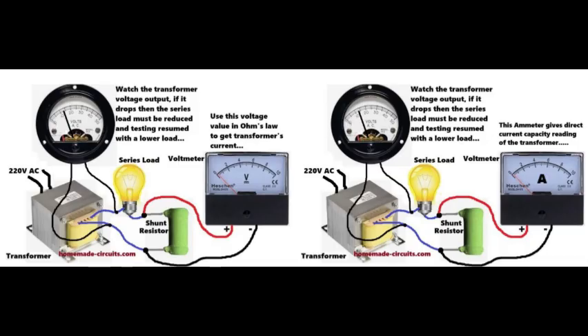Example calculation. Let us say we put a 0.05 ohm shunt resistor. Now, during the test, we measure voltage drop across shunt equals 0.75 volts. So current equals 0.75 divided by 0.05, which is equal to 15 amps. If transformer output is still near 12 volts and heating is moderate, then we say this transformer can give 15 amps safely. But if at that point the transformer body is getting hot or buzzing or voltage dropped below 11 V, then we stop and say transformer max current equals maybe 12 amps. So we decide that 12 amps is safe, 15 amps is risky.